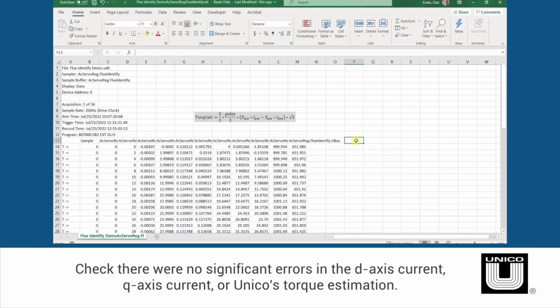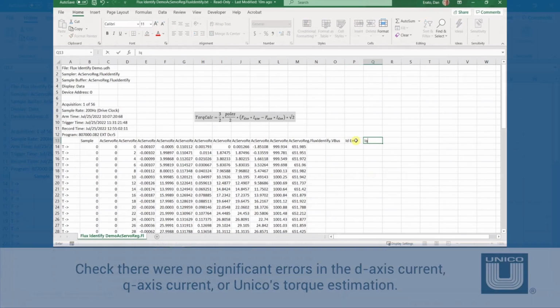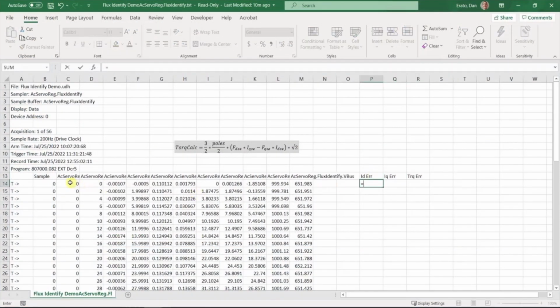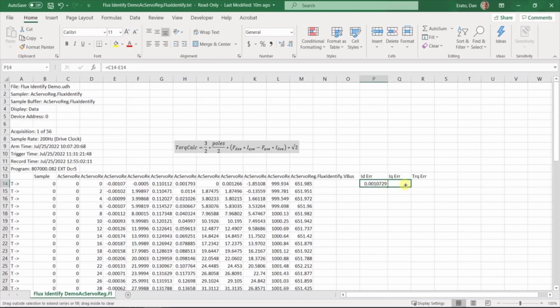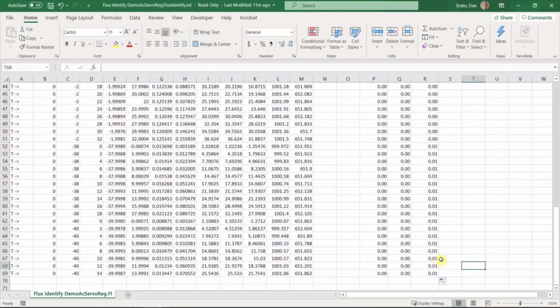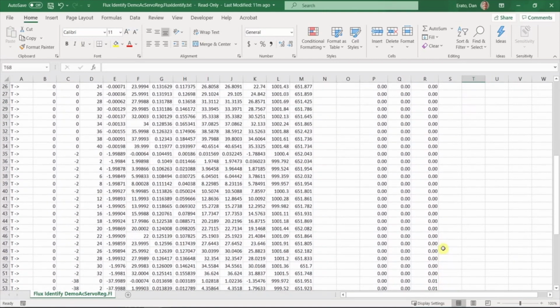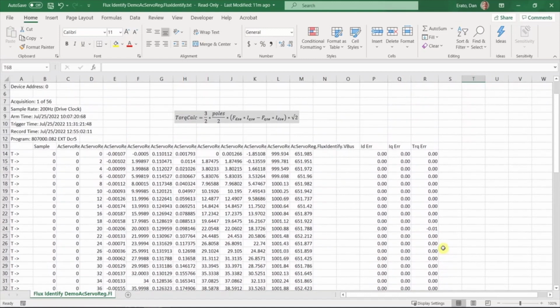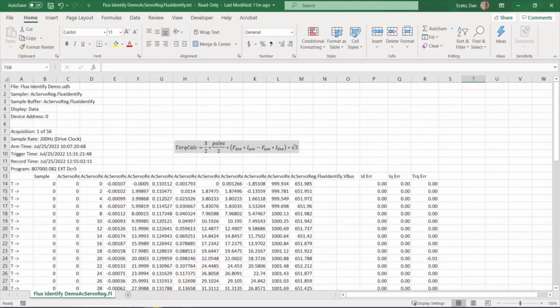Anyways, next check there was no significant errors in the D-axis current, Q-axis current, and Unico's torque estimation. The ID error is the difference between the request and feedback. Similarly, the IQ error is the difference between the request and feedback. Lastly, the torque error is the difference between the calculation and the feedback. Visually check the spreadsheet calculations to ensure there are no significant errors. It is important to check these errors, especially when troubleshooting the IDQ command tables.